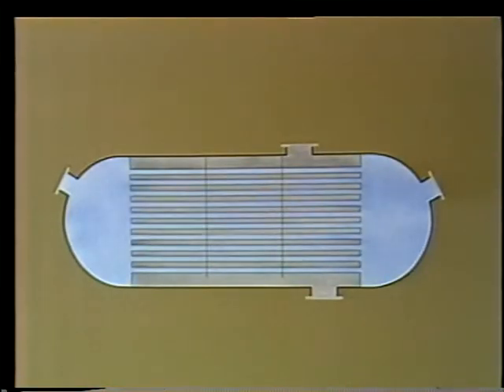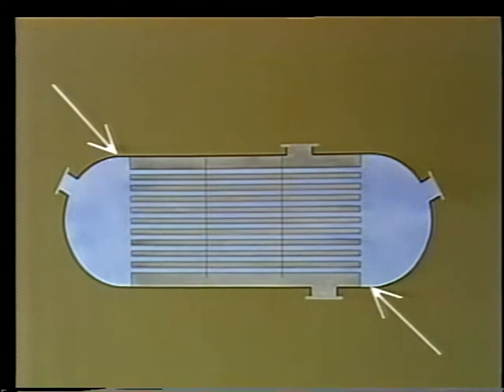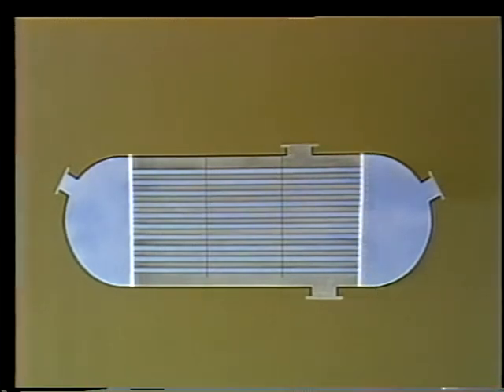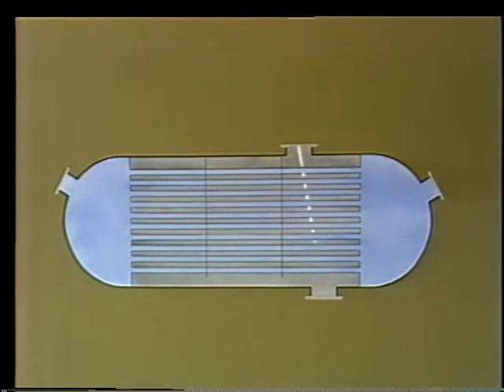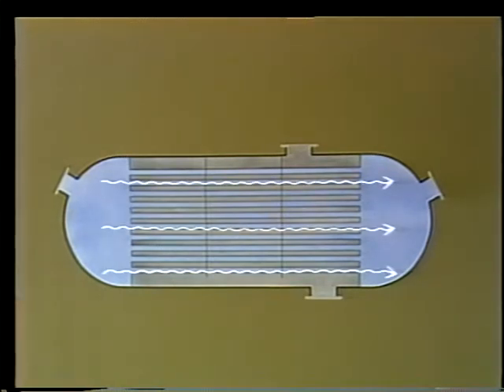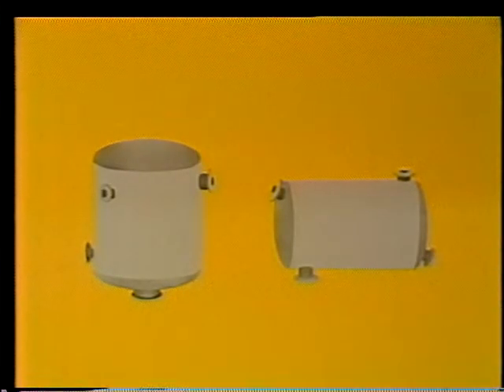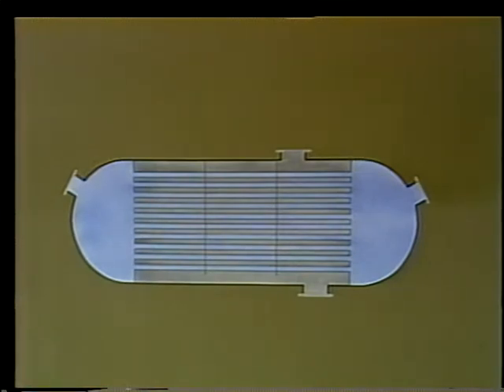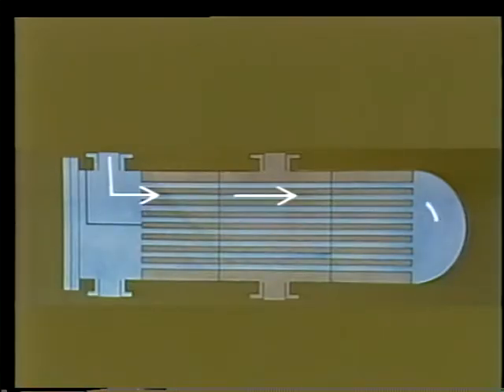Shell and tube heat exchangers are similar to condensers in many ways. The shell is the main body of the heat exchanger and holds the tubes and tube supports. The tube sheets isolate the water box and support the tube bundle at its ends. When we refer to the shell side, we mean the area within the shell and around the outside of the tubes. When we talk about the tube side, we're referring to what goes through the inside of the tubes. Shell and tube heat exchangers come in many different styles depending on the purpose for which they're designed. They may have either a vertical or a horizontal shell, and they may be single pass or multi-pass.